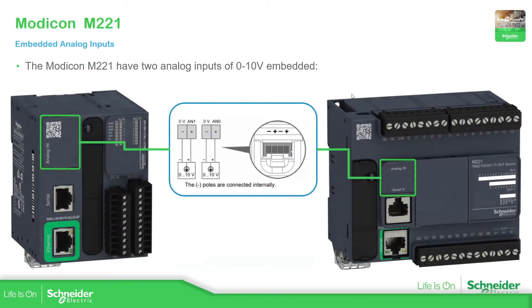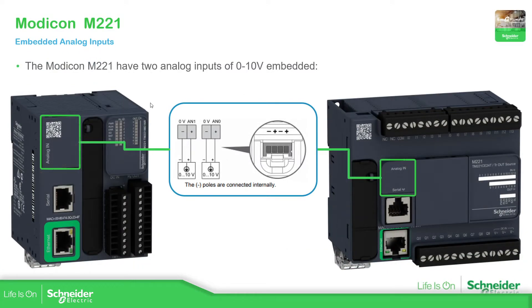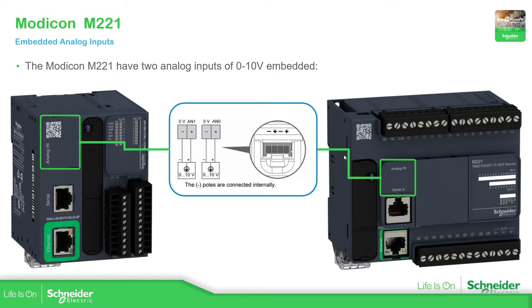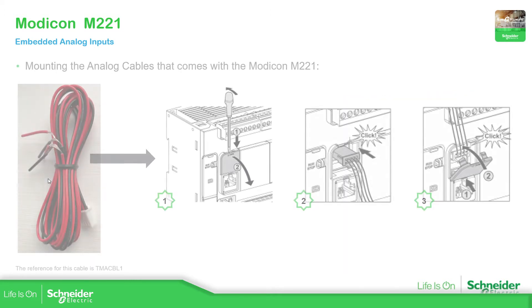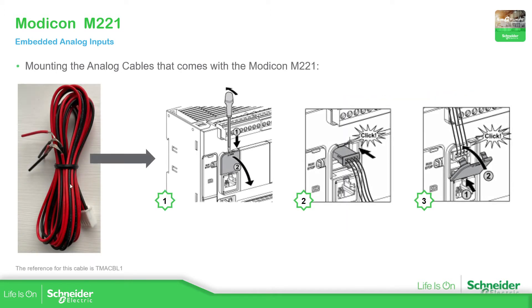Depending on the M221 that you have, the location of the analog inputs are changed. In any M221 you have two analog inputs, as you can see here, and the type of analog input is voltage from 0 to 10 volts. There is a cover in front that we can remove. This is the process to remove it - just use a screwdriver, remove it.